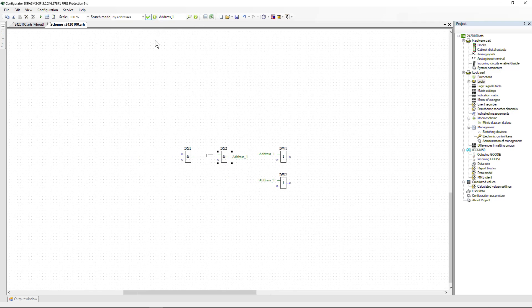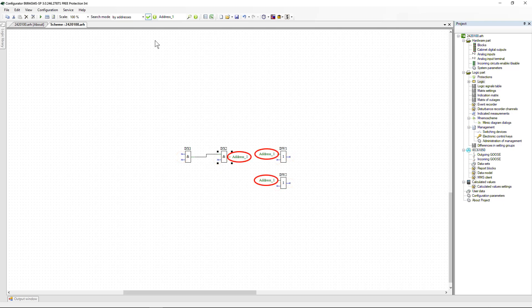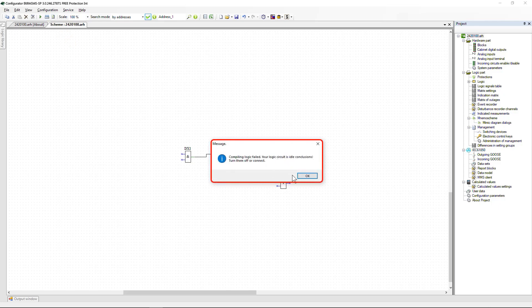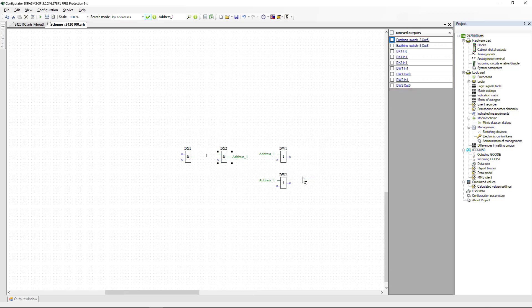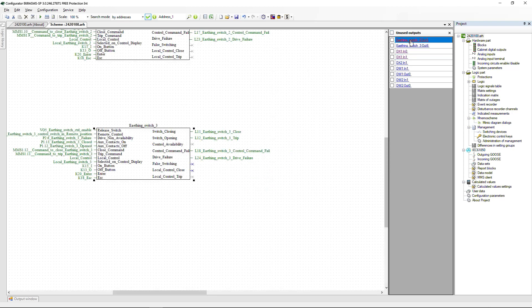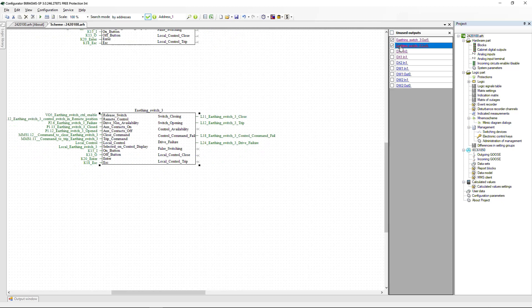When editing the logic diagram, pay attention to the colors of element inputs and outputs. If an input or output is highlighted in blue and marked with a cross, it is not connected to any other element or not added to the signal table of the IED. Highlighting in green means it is connected. To correctly create logic, there must be no unconnected inputs or outputs. You can check this by compiling the logic — if unconnected items are found, a message will be displayed. Unused inputs or outputs of functional units or matrices can be disabled by checking the corresponding box; disabled inputs/outputs are ignored during compilation.